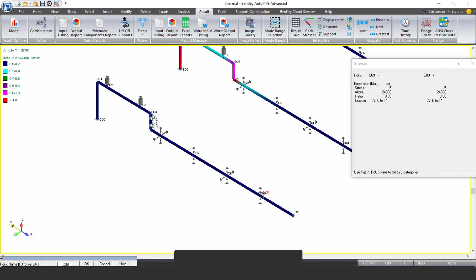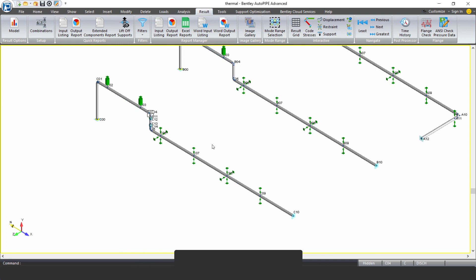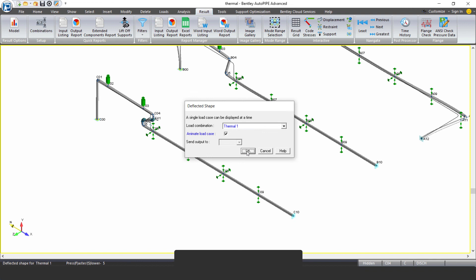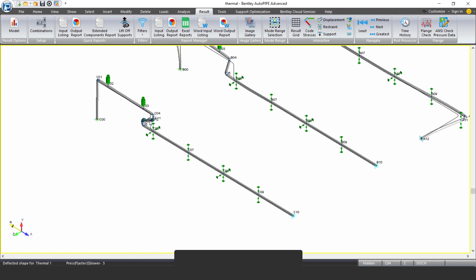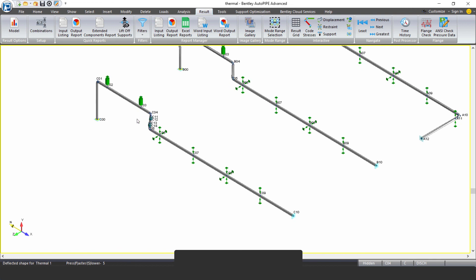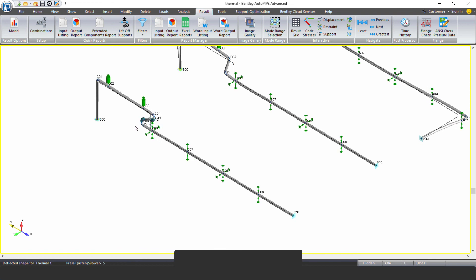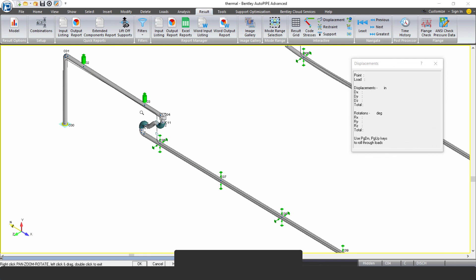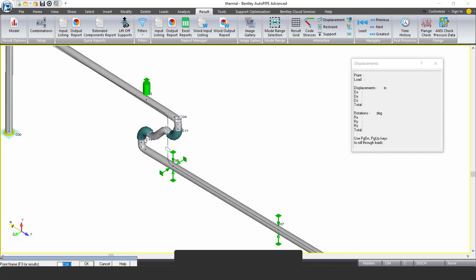Basically a ratio of zero throughout. Very, very low. So that's great. That's what the expansion joints have allowed us to do. We could assume these are maybe like two hinge expansion joints working together. The pipe is guided nicely, but let's look at the displacement. If we do our thermal growth here, we see some decent displacement throughout that vertical section of pipe where those expansion joints are allowing that movement.